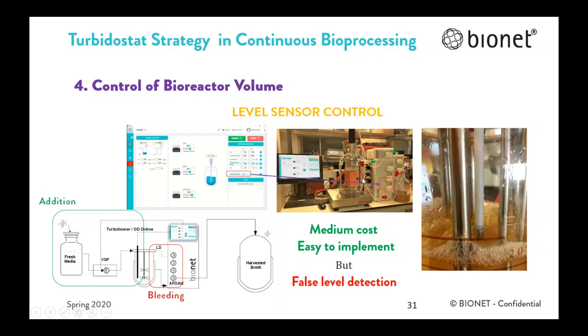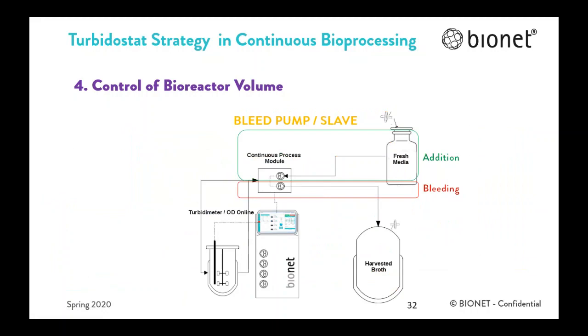The level control by a level sensor can be achieved with level probes. This is an example of a setup with a benchtop bioreactor using the level sensor to detect and control the volume. In this particular configuration, the pump is used to control the level by connecting the tubing of the outlet stream from the bioreactor to the harvest bottle. The limitations of level probes are that they are subject to false level detection when foaming occurs within the bioreactor, and for that reason the precision can be less than other systems like weight control.